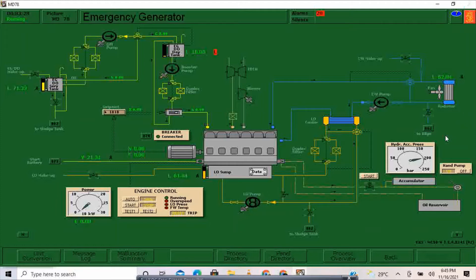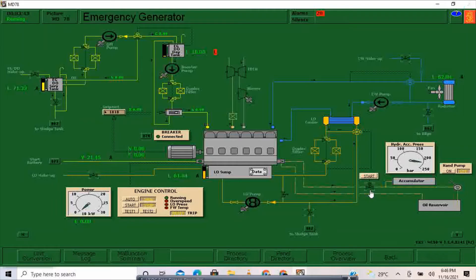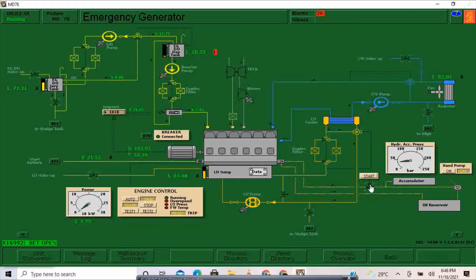Almost there — almost 200 bars. Now it's 200 bars, so I'll stop doing the hand pump. We are ready for the hydraulic start of our emergency generator. To start hydraulically, I will click start. Our emergency generator is now running.